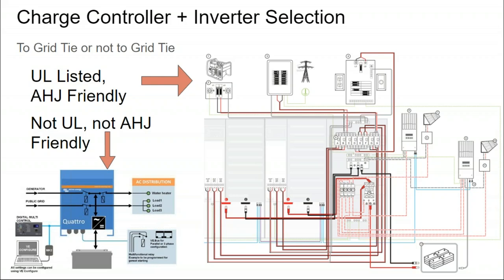They'll also have their own AC separately derived output. So there can be an inverter powering an entire structure that does not have any grid synchronous ability at all - it's not listed for a grid connection. On its back side, there might be a separate AC side grid charger just to keep the batteries topped off from the grid side. But everything coming out of the battery inverter is one way, and it only meets the load.